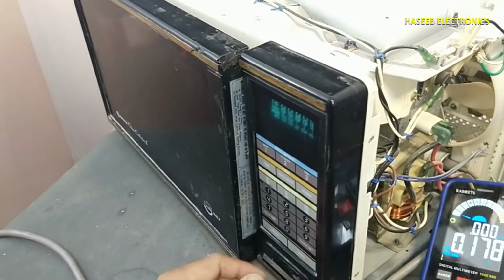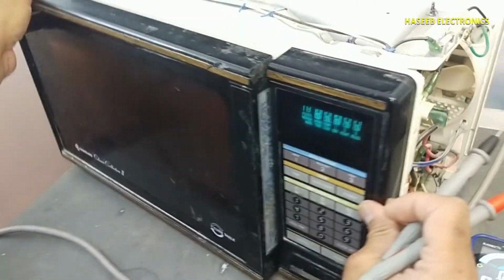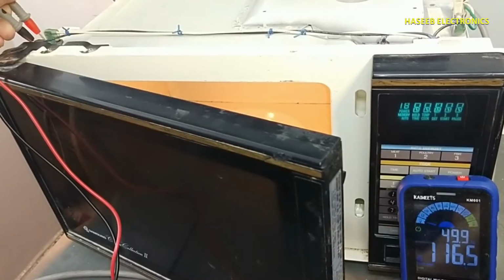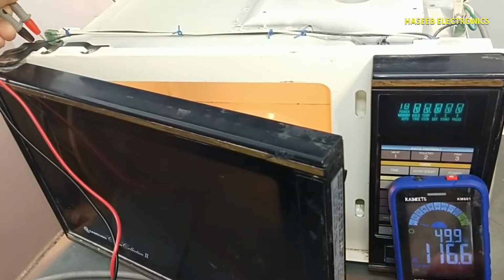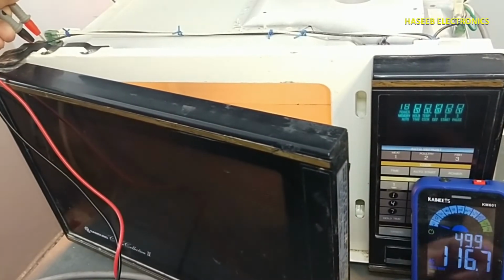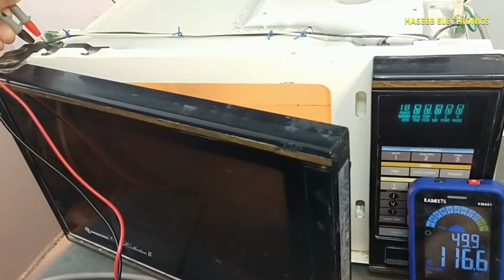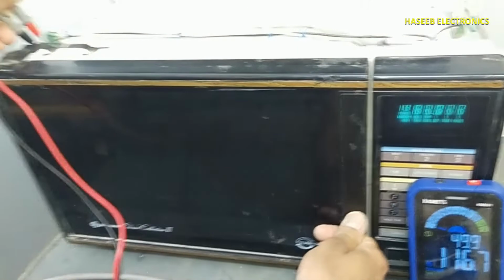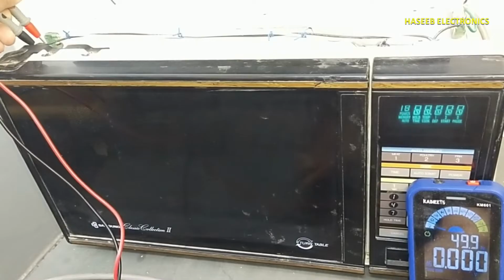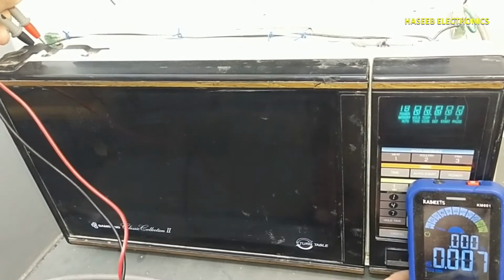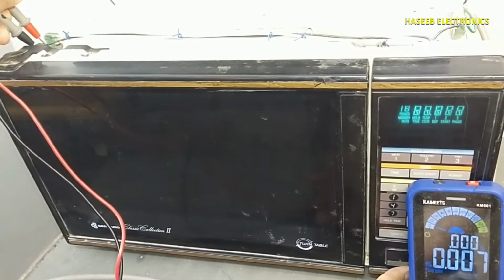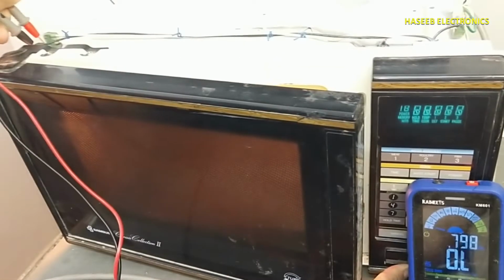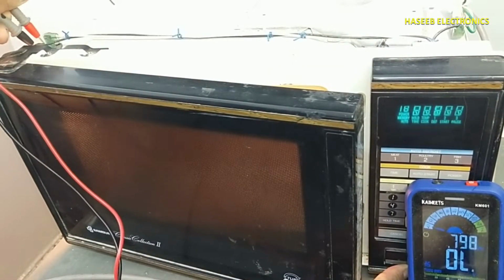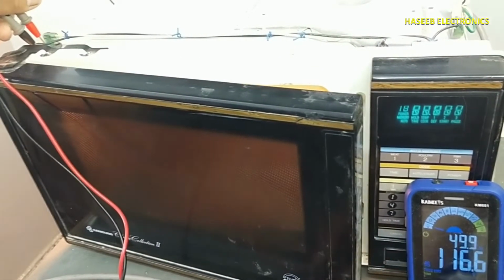Set the multimeter to AC voltage. When the door is opened, it will provide 115 volt, 120 volt at the lamp. When the door is closed, the relay will turn off and voltage will not appear. When the door is opened, the relay will turn on and voltage will reach here.